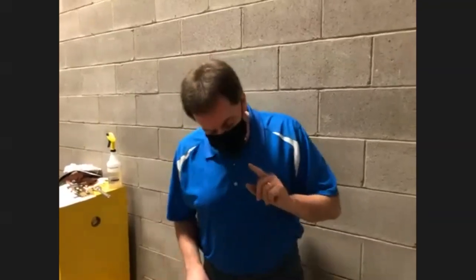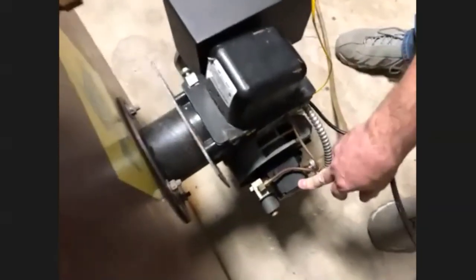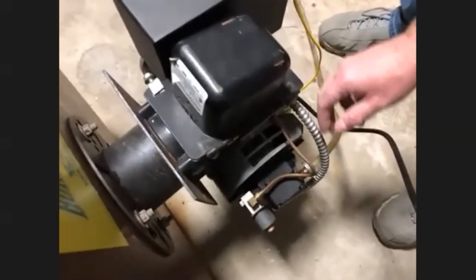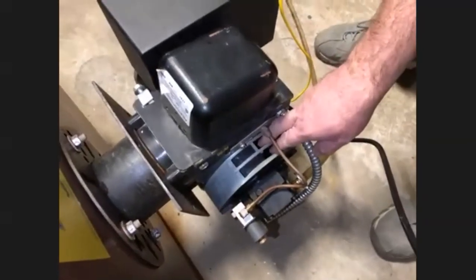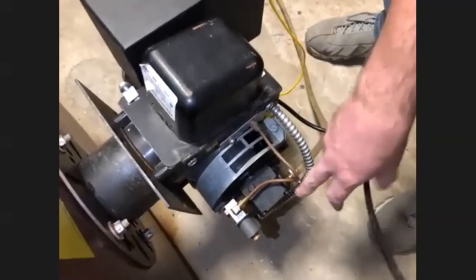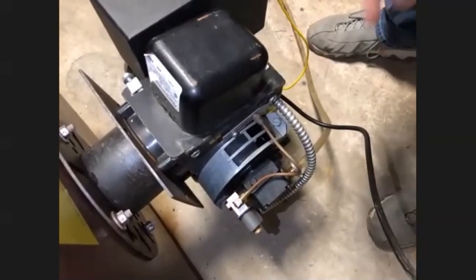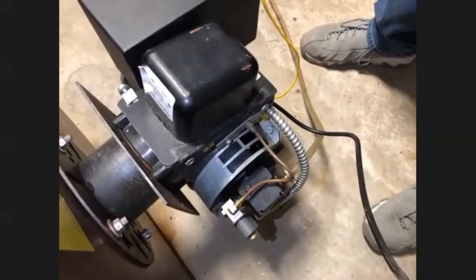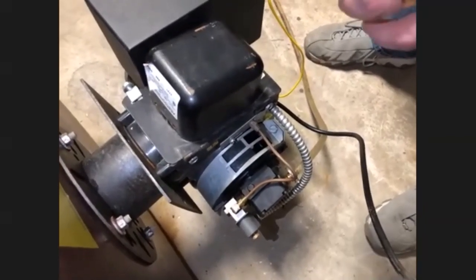One other thing I missed on the troubleshooting, when you do operate these, if you're not getting any flow through the pump, it's very possible that there is a connecting rod in there that connects the blower to the pump. That may be loose. There's a set screw on it to the shaft. It's a little coupler. You just tighten that up.